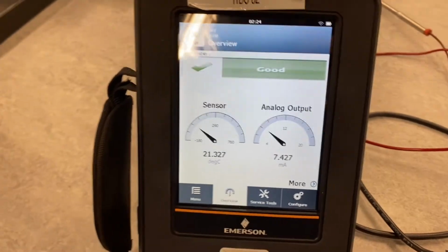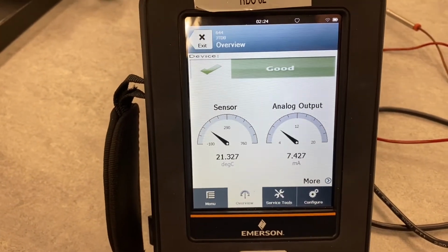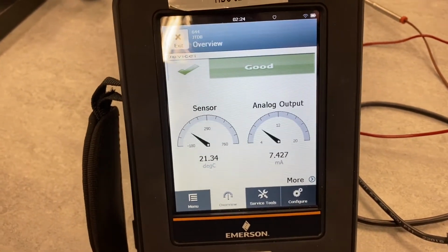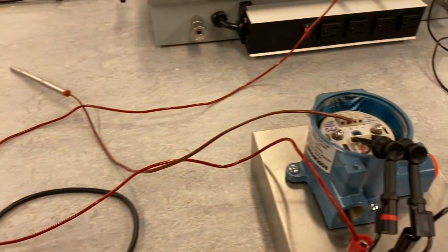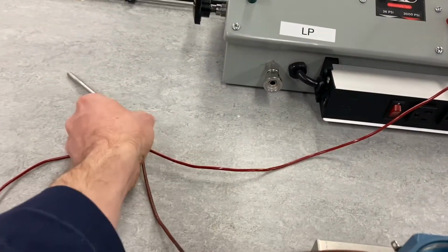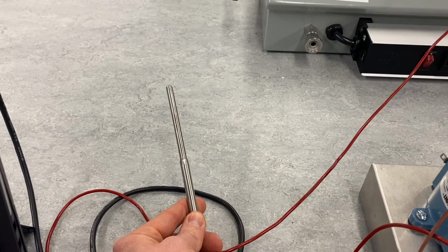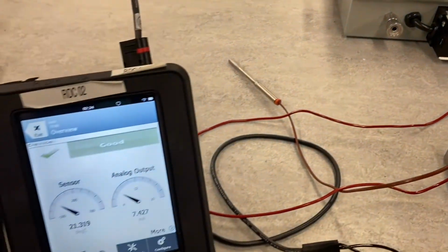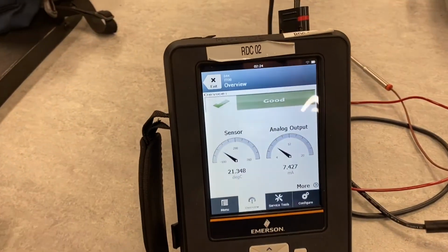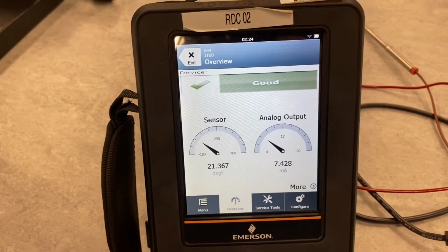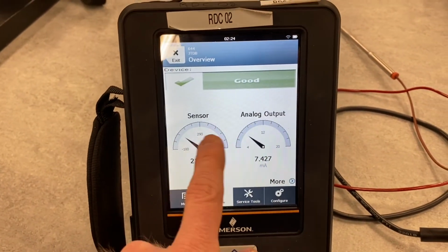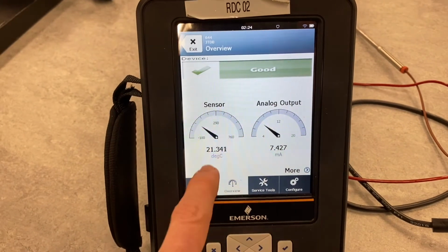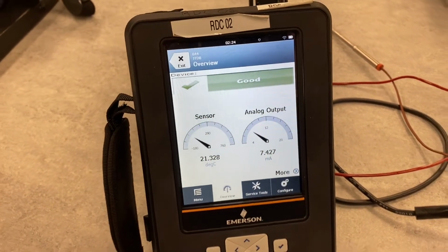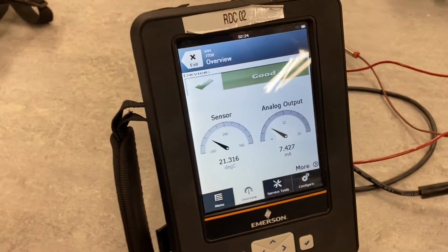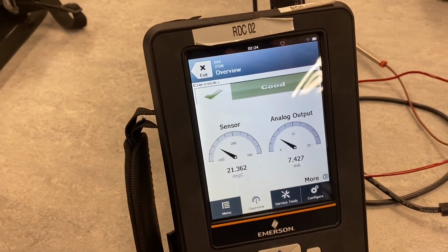And so what we're going to want to do here as well is verify. We're not going to do calibration here. We're just going to verify that the transmitter is working correctly by inserting the thermocouple into an ice bath and also into our dry block at either 100 or 125 degrees C. And we should see the temperature change here to the right value to verify it. We should be able to verify within at least about 2 degrees Celsius.